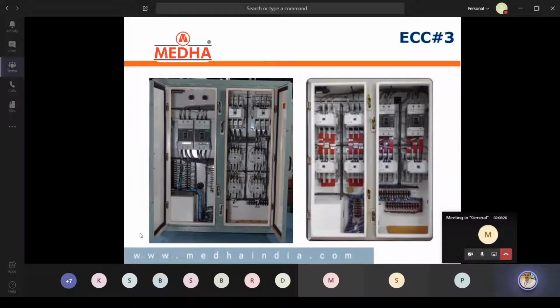And as per the engine temperature, the system first drives slow speed contactor 1. So the system energizes this, then the radiator fan runs at slow speed. Further, if the temperature is unable to be controlled, as per the logic, number 2 will also be driven at slow speed, and after 20 seconds if the temperature is still not within the range, not decreasing in trend, then the system drops the slow speed contactor and picks up the fast speed contactor FCF 1A. With the interlock of 1A, it drives 1B.